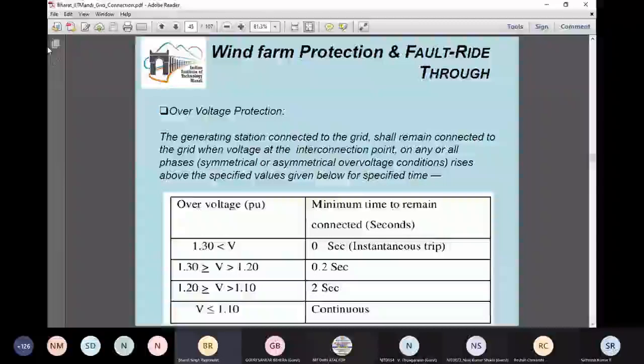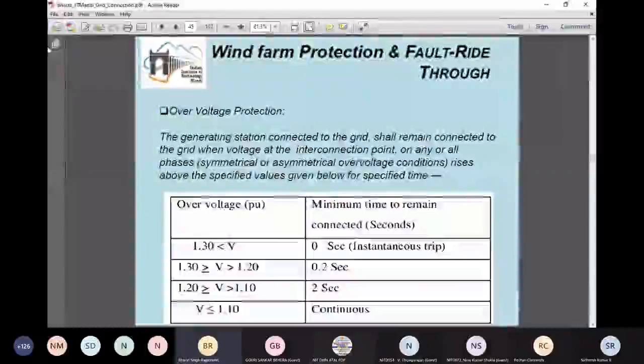This particular slide is about when the voltage is beyond the specified voltage, known as high voltage ride-through, HVRT. The previous curves were for LVRT, low voltage ride-through. If the voltage is beyond specified values, the wind farms can also get disconnected. For example, if the voltage is 1.30 per unit, then there is an instantaneous trip. But if the voltage is around 1.10, there should not be any disconnection. Next slide, please.